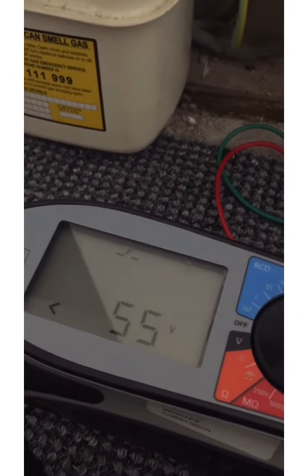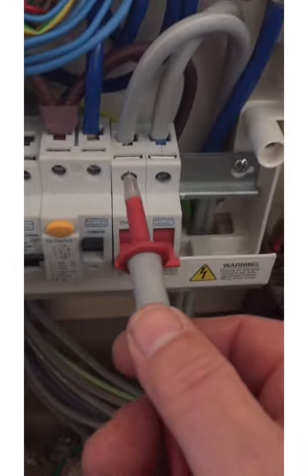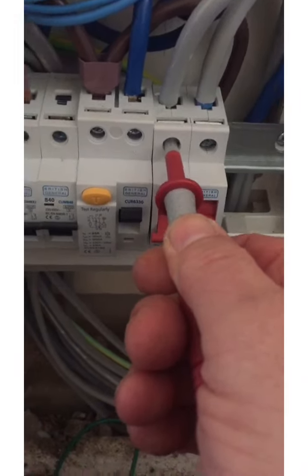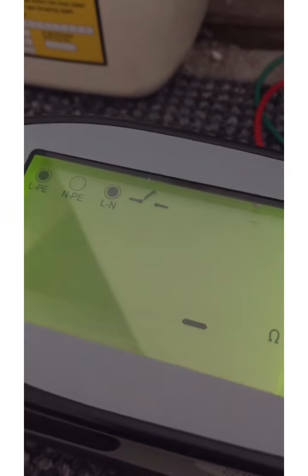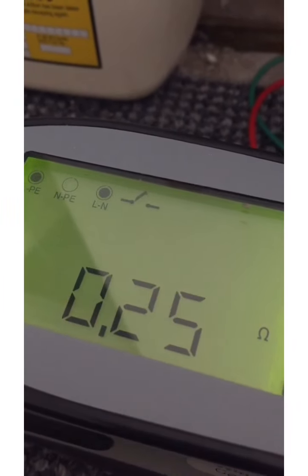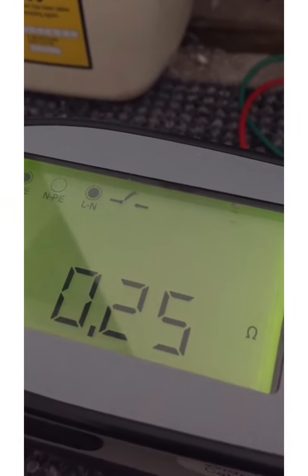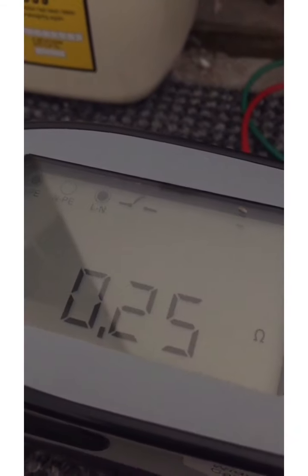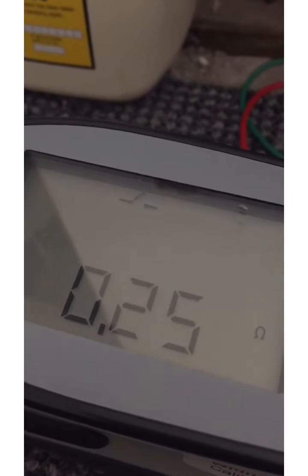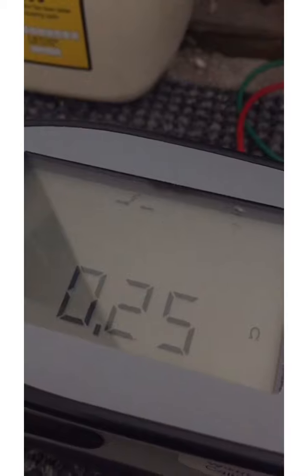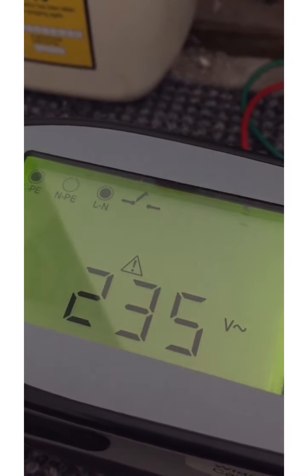So it's telling us there, less than 55 volts, because obviously it's not at the moment connected to the supply. When I put the probe on, it's going to initiate automatically. Let's have a look at that. So I'm getting 236 volts, 0.25. So our ZE is 0.25. Let me just take that again. So what have we had so far? 0.23, 0.25. Let's go again. 235 volts.